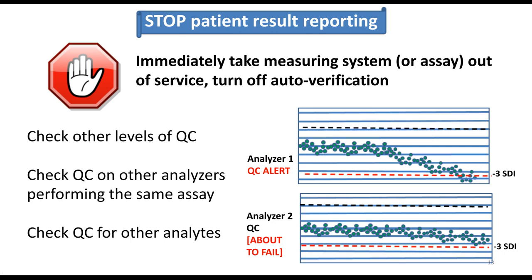Once an alert is detected, the technologist should ensure that all patient result reporting is stopped for that assay. This could include taking the assay out of service or even taking the entire analyzer offline if necessary. Be sure to turn off auto-verification, if auto-verification is performed in your lab, so that results are not automatically reported into the medical record.